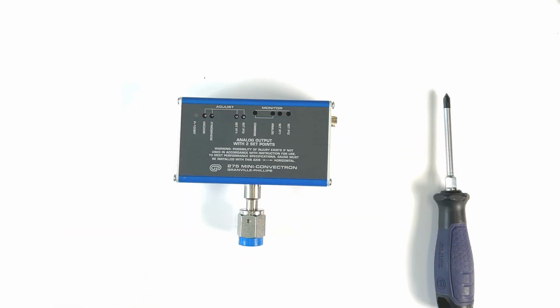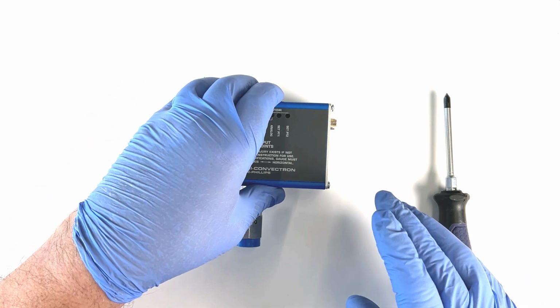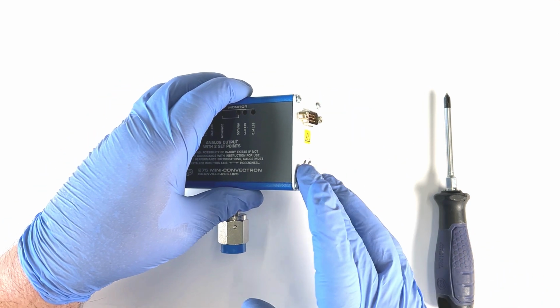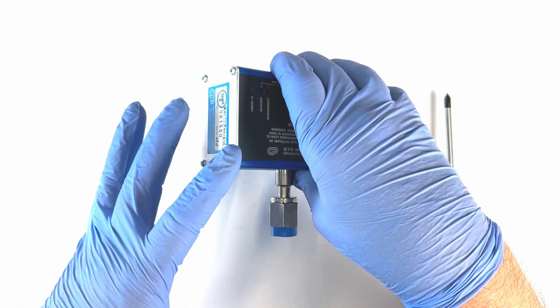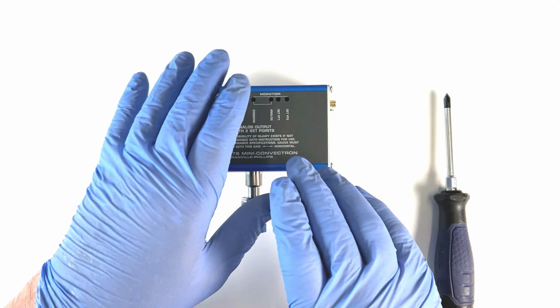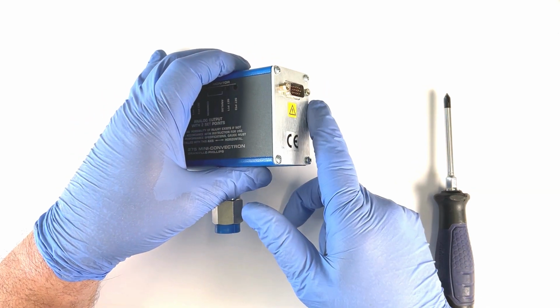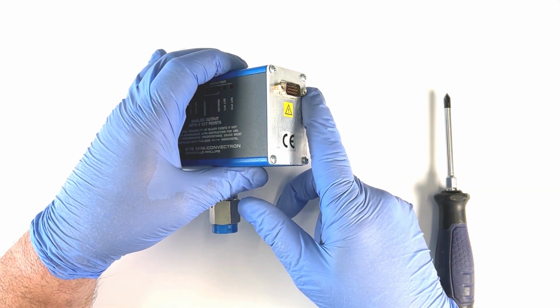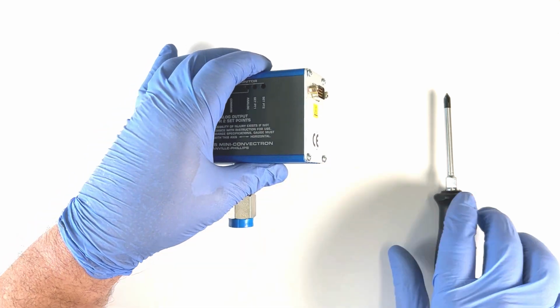Before beginning the procedure, turn off the power supply, then disconnect power from the module. Vent the vacuum chamber to atmospheric pressure and remove the module from the chamber. Next, remove the 4 Phillips head screws from both module end plates, but do not remove the hex nuts that hold the D subminiature connector in place.